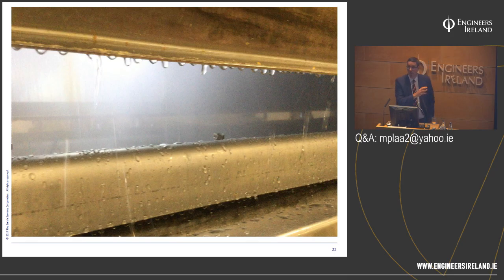One of the most common failures we've found is when the system gets discharge tested. On all of our fryers and ovens, we will undertake full discharge testing to check the functionality of the system, run the system for 5 to 10 minutes and make sure all the nozzles are clear and we've got a correct spray pattern. We will do that on all new projects.